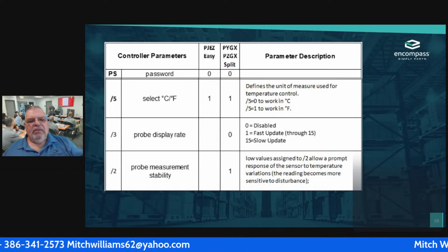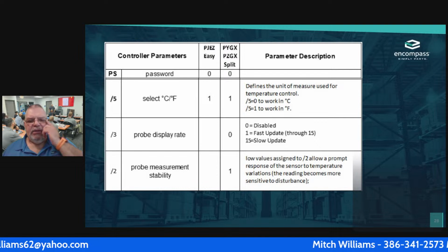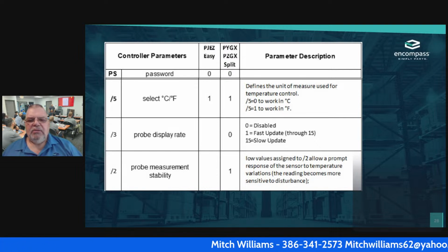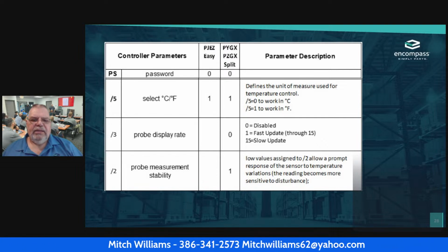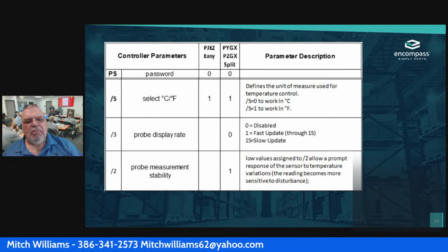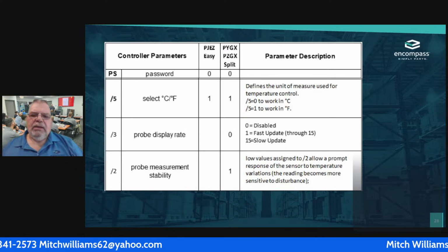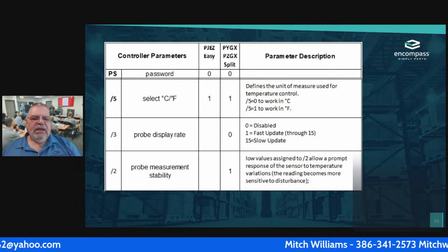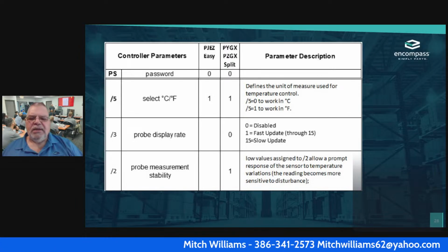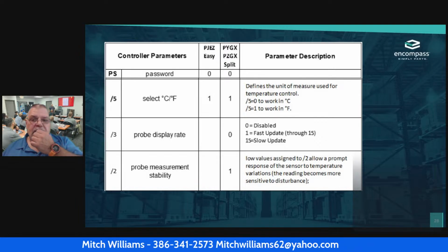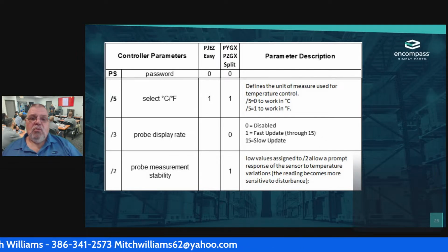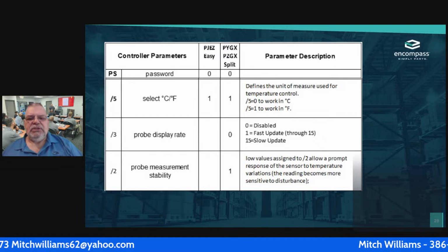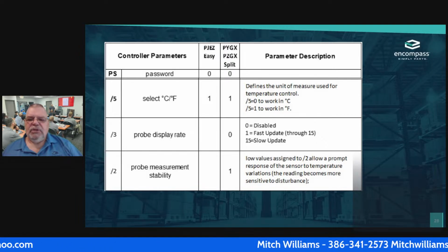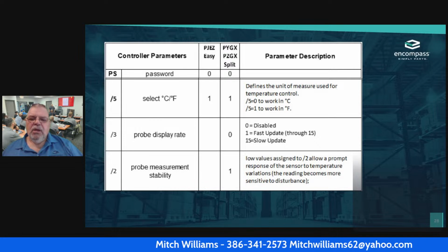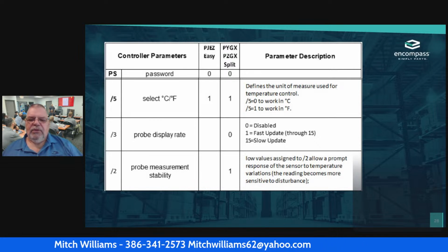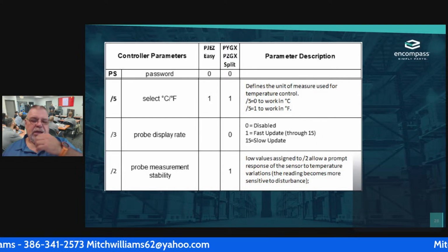Okay. The /5, once again, that's either Celsius or Fahrenheit. It comes with 1, which is Fahrenheit. But if I want it in Celsius, I can go back in, find the /5, and put a 0 in it. If I get a /3, that's the probe display rate. Okay. It's only valid for a PYGX or a PZGX. That's set for a 0. That means it's disabled. 1 is a fast update through 15.